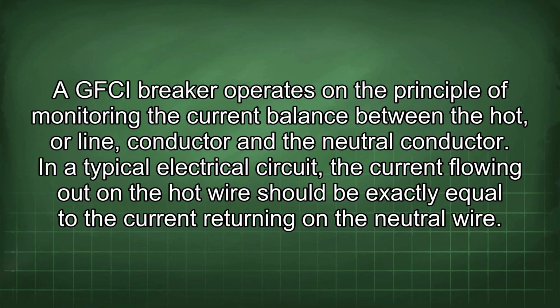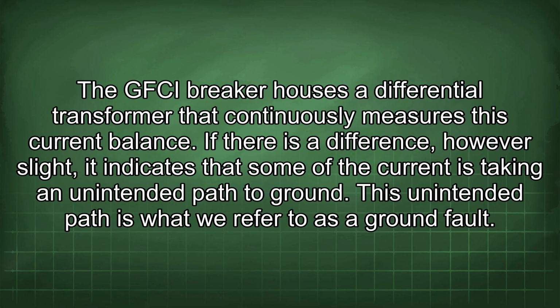In a typical electrical circuit, the current flowing out in the hot wire should be exactly equal to the current returning on the neutral wire. The GFCI breaker houses a differential transformer that continuously measures this current balance. If there is a difference, however slight, it indicates that some of the current is taking an unintended path to ground. This unintended path is what we refer to as a ground fault.